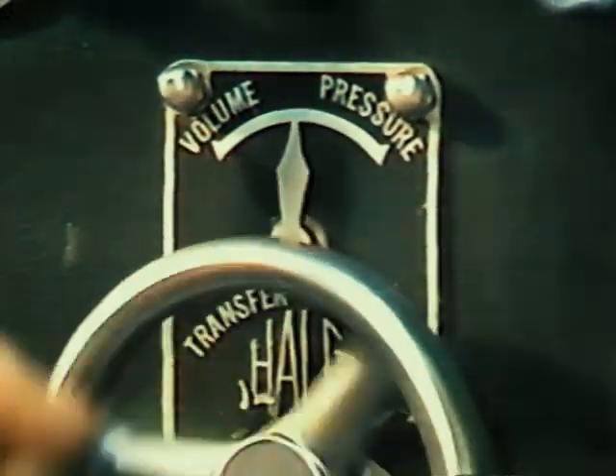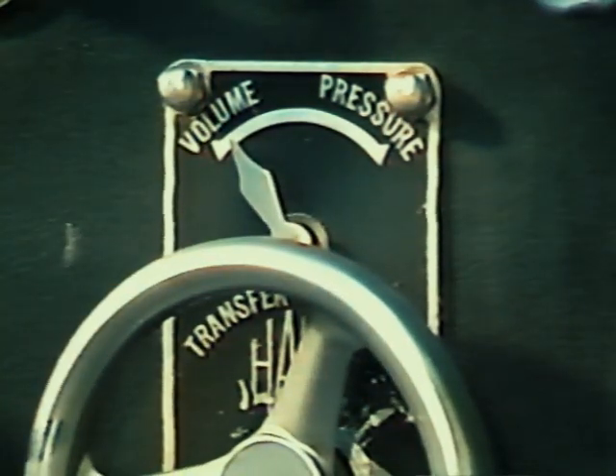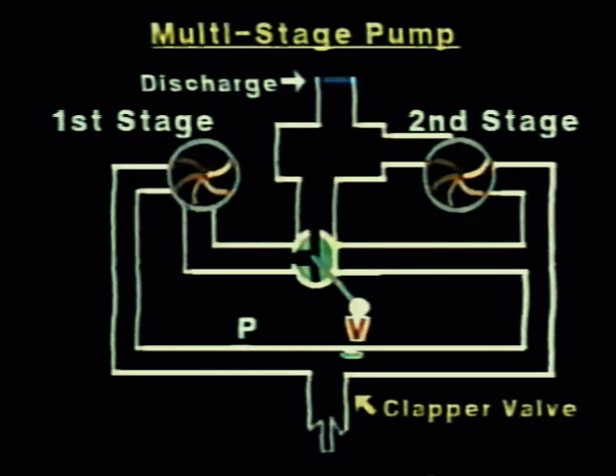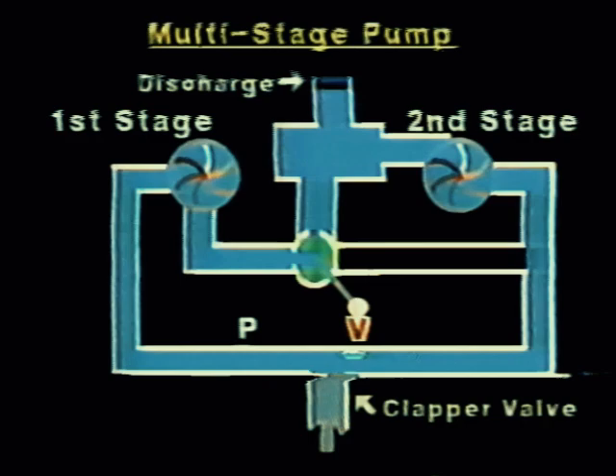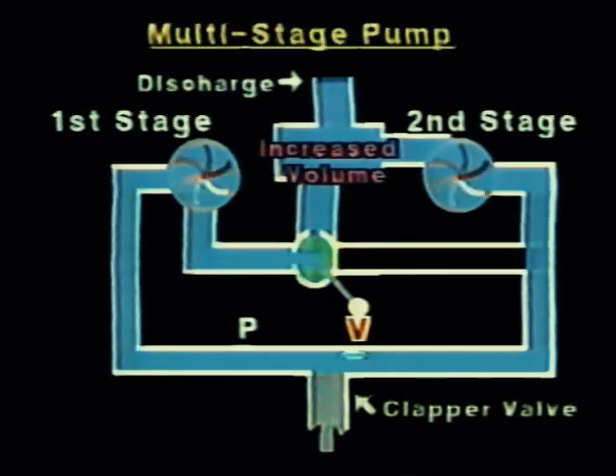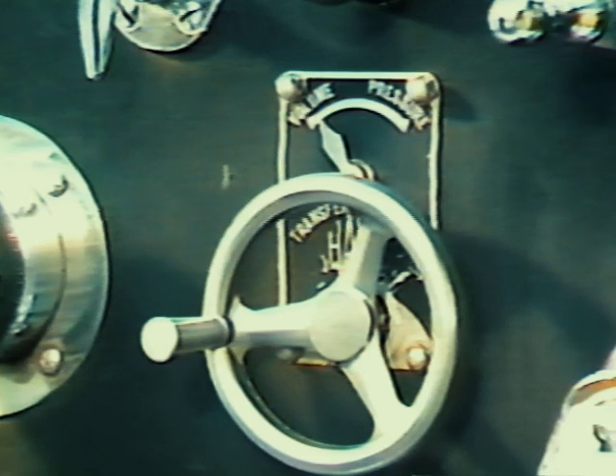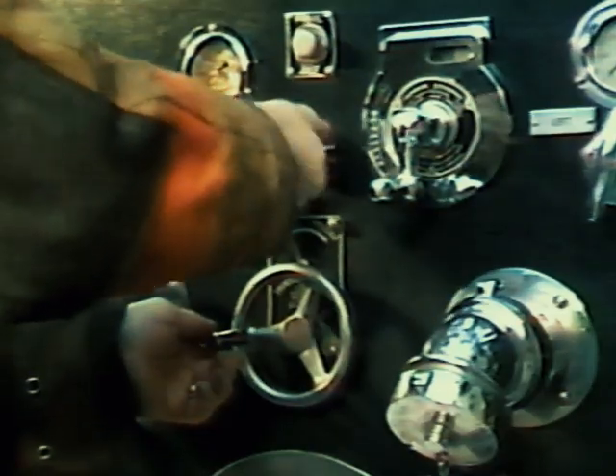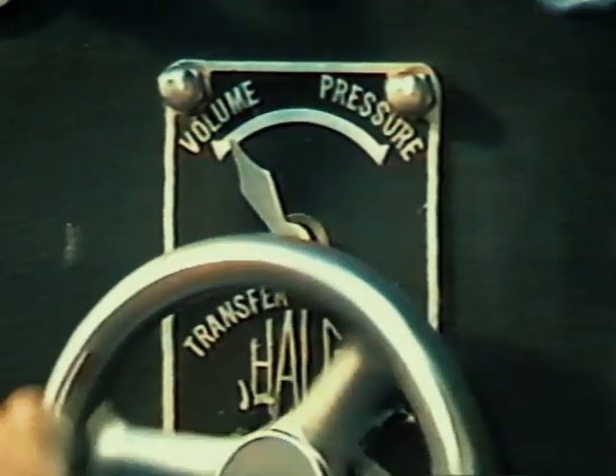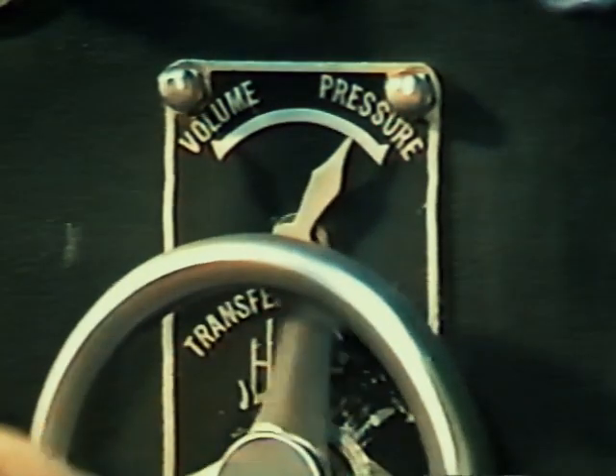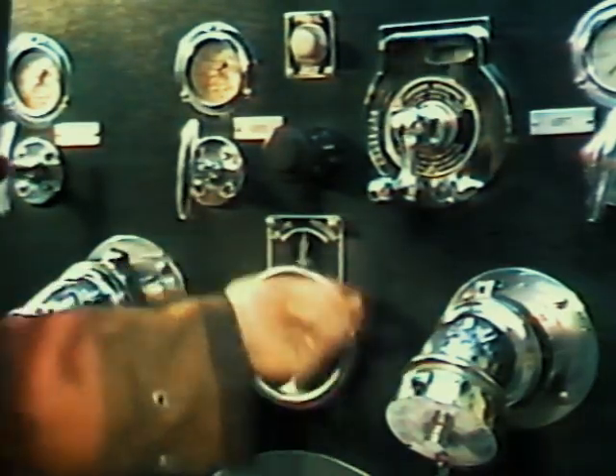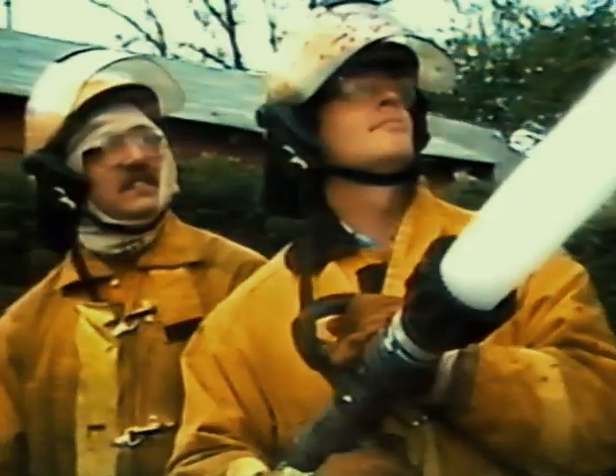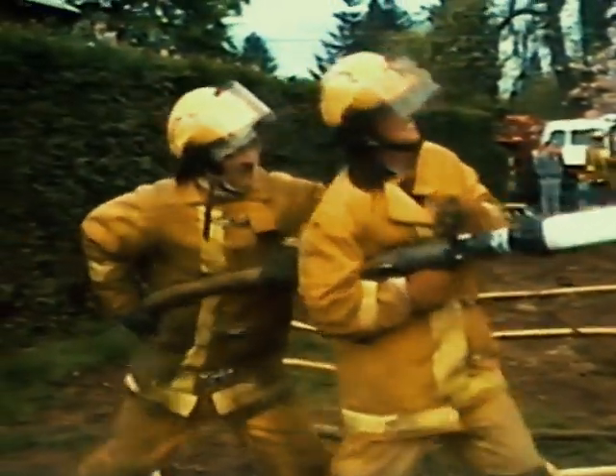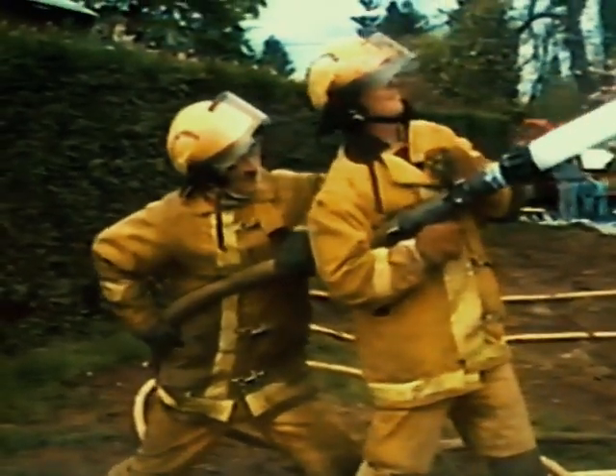To increase volume, place the valve in the volume or parallel position. The valve channels 1/2 of the total water available to each stage of the pump. Each stage operates as a single-stage pump that increases the volume by discharging the water to a common discharge. Care must be taken when switching from one setting to the next. Use the throttle control to slow the pump and lower the water pressure. This is especially critical when switching from volume to pressure. Switching from volume to pressure when the pump is running at capacity may result in a pressure surge in the hose lines that may jeopardize the safety of the nozzle operators or damage the pump.